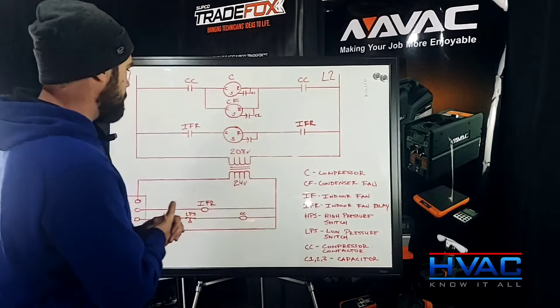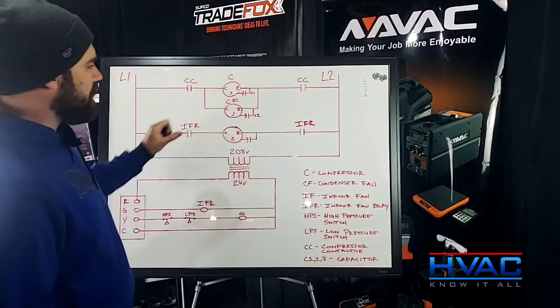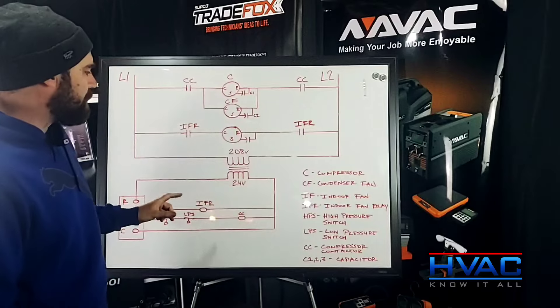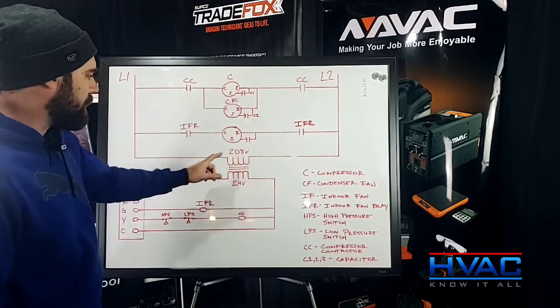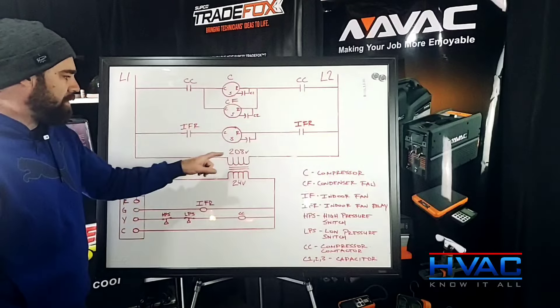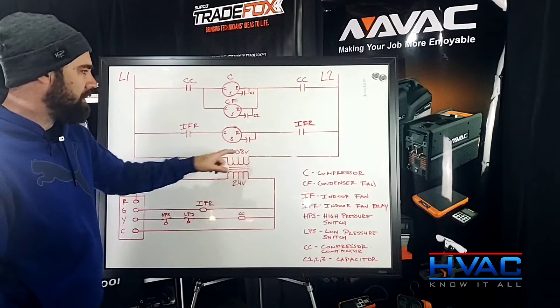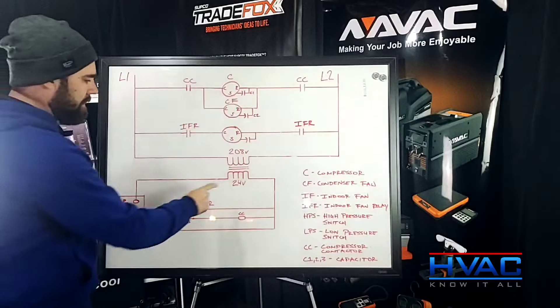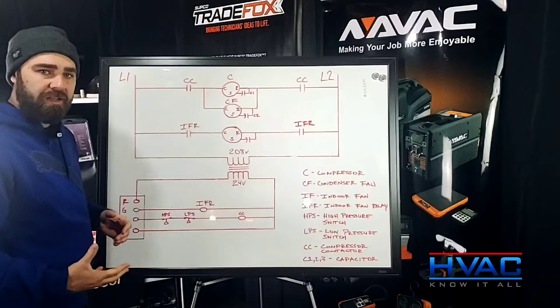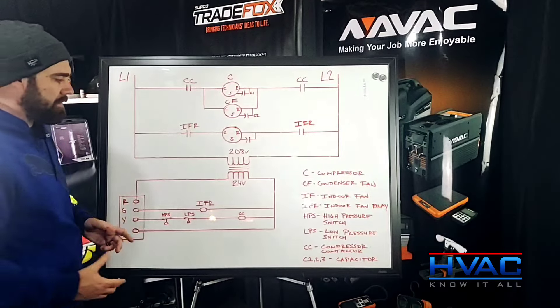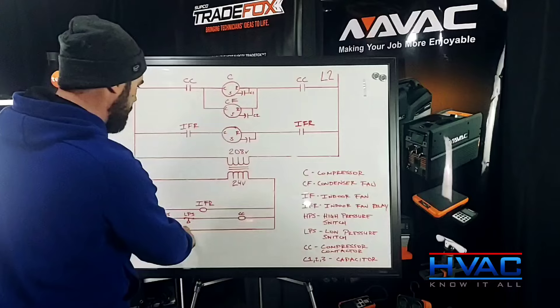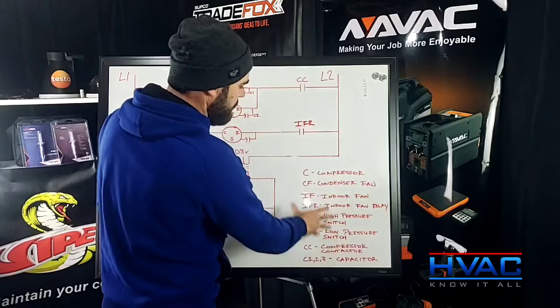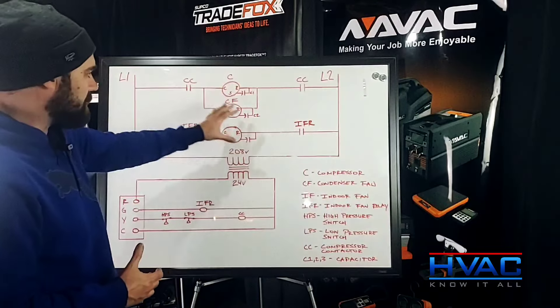Okay, so the diagram. We have a high side — when I say high side, this is our high voltage side. This is our low voltage side. It is separated by a transformer. I've written the voltage at the top and the bottom of the transformer. The primary voltage of the transformer is 208, so we can presume that this circuit here is a 208 circuit. And then the low side at the bottom is going to be our secondary voltage or our control circuit — that is 24 volts. So the other thing we've done for you here is put in a legend. Legend is very important — if you don't have that, sometimes you might not know what some of these things mean.